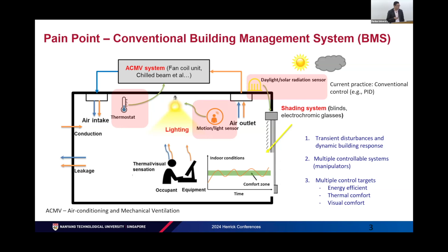That is where our MPC, or model predictive control, comes in. There are multiple systems in the building you want to control, and you have to operate within certain constraints required by the building or users, along with multiple disturbances acting on the building that typical PID control systems are not able to account for.